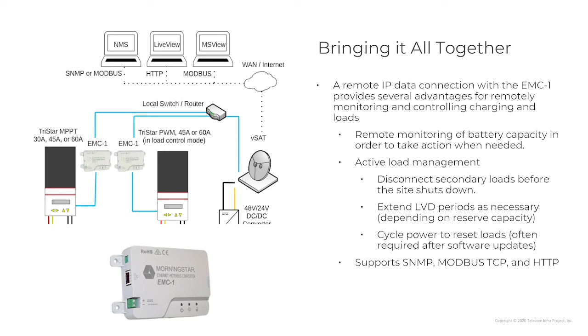The granularity of the data that you actually gather is pretty critical. We've seen everything from every 15 minutes to hourly polling, to extensive sites where they're looking to really model a type of system, and they want extremely high granularity of data, meaning polling every 5 to 10 seconds. Because if you don't have the resolution, you will often miss transients or things that occur in the power system that just won't get picked up because you didn't sample at a high enough rate. And that's extremely useful to be able to catch that.